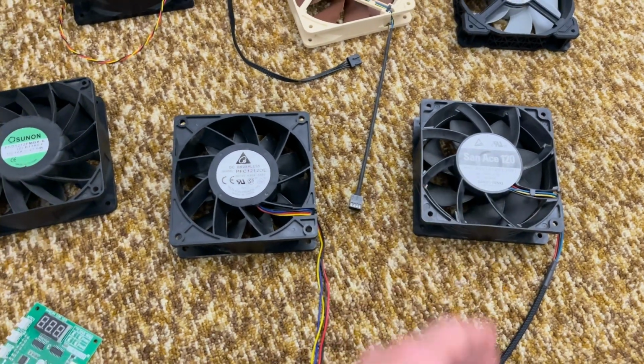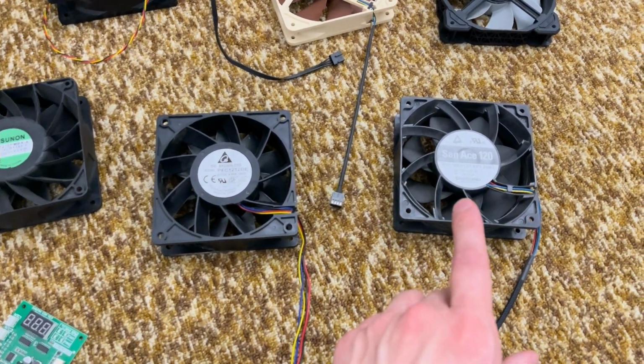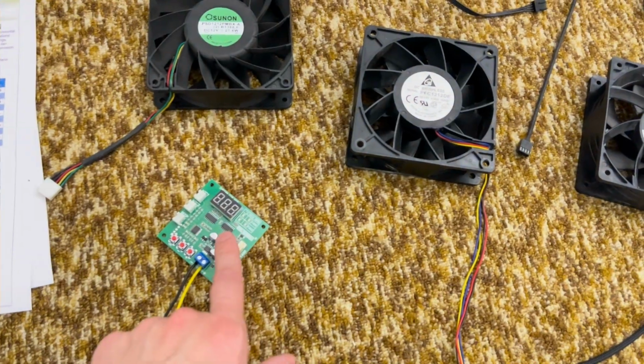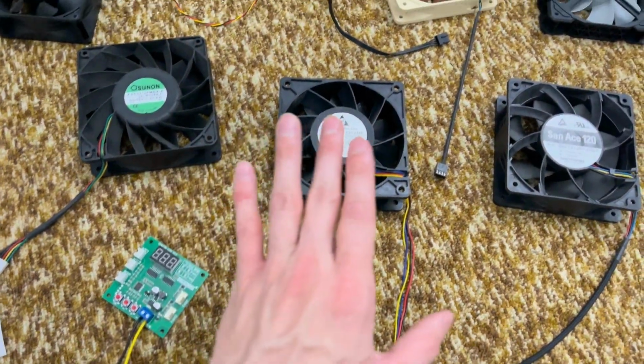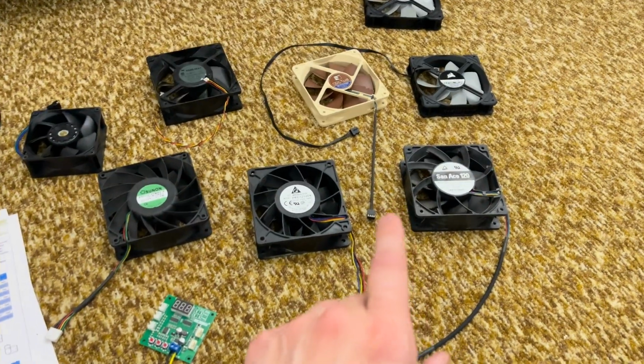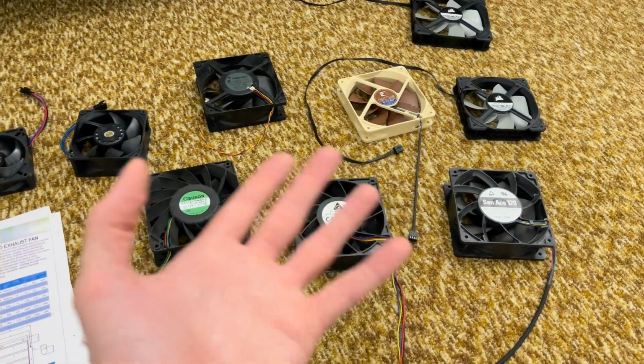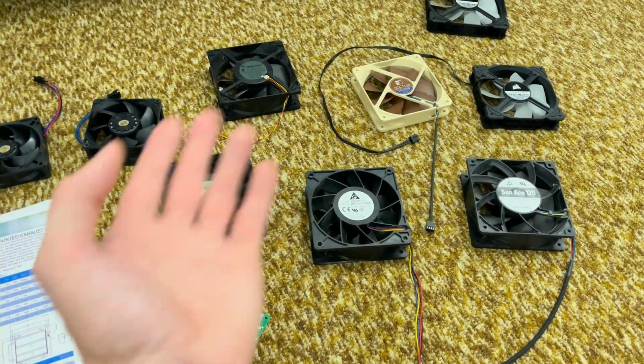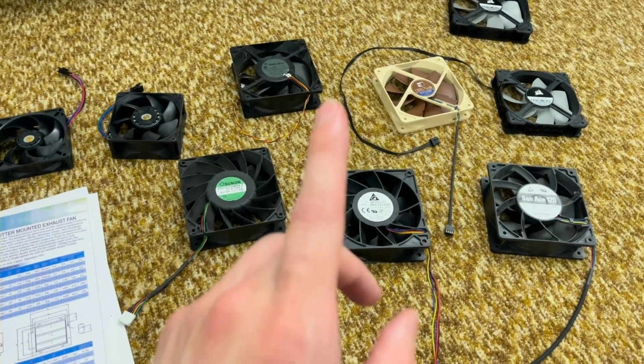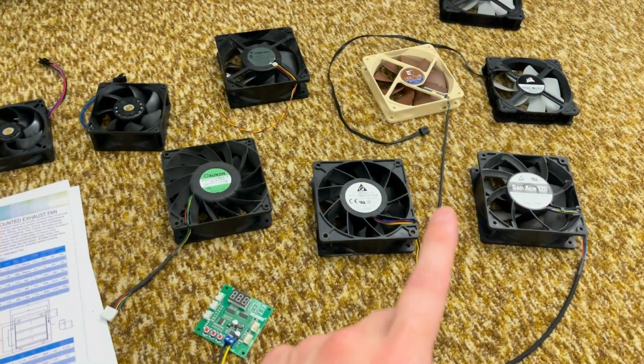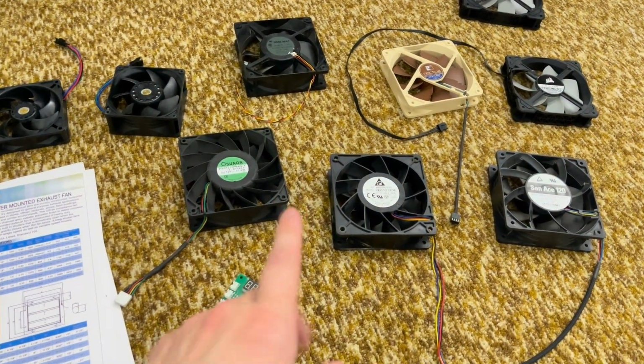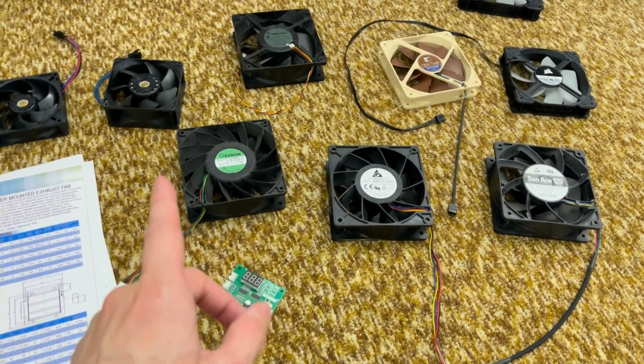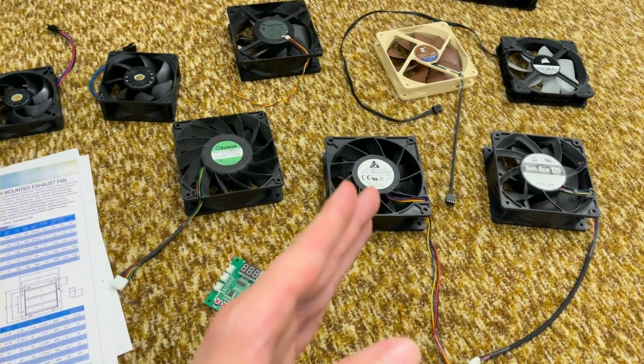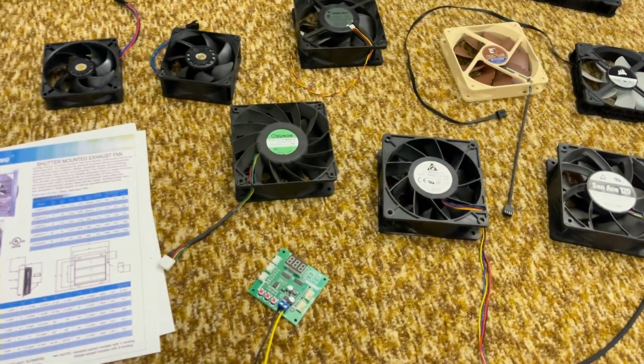I need a high power fan that has deep throttling capabilities, because then you could just throttle it down. And typically fans are actually most efficient somewhere in the range of half speed. Maybe higher, maybe lower, depends on the fan. But a lot of times, a fan that's overrated but slowed down will be more efficient than a lower power fan run at full speed. Something to watch out for.